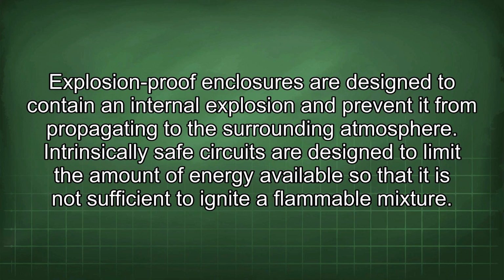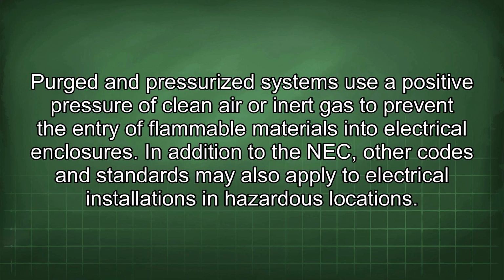Explosion-proof enclosures are designed to contain an internal explosion and prevent it from propagating to the surrounding atmosphere. Intrinsically safe circuits are designed to limit the amount of energy available so that it is not sufficient to ignite a flammable mixture. Purged and pressurized systems use a positive pressure of clean air or inert gas to prevent the entry of flammable materials into electrical enclosures.